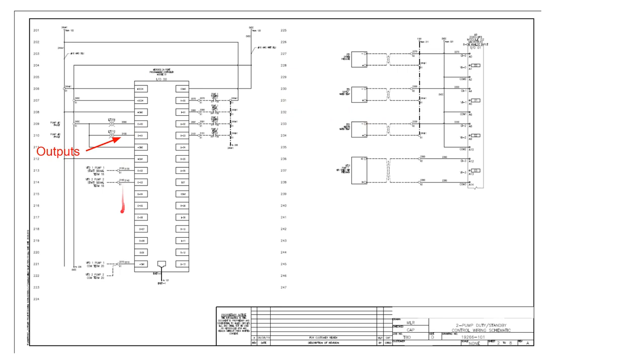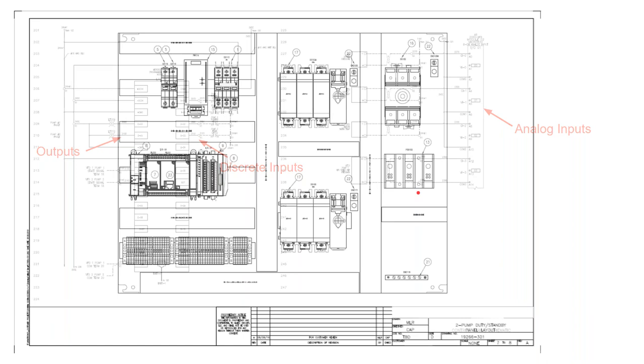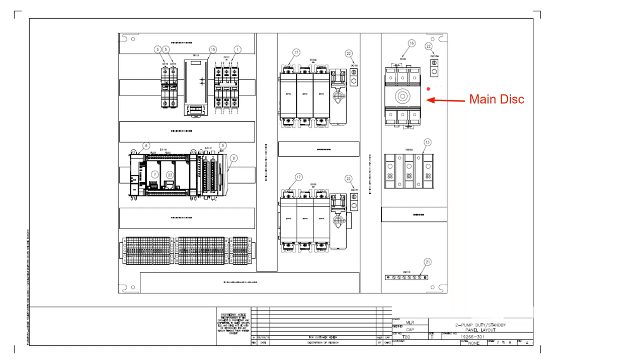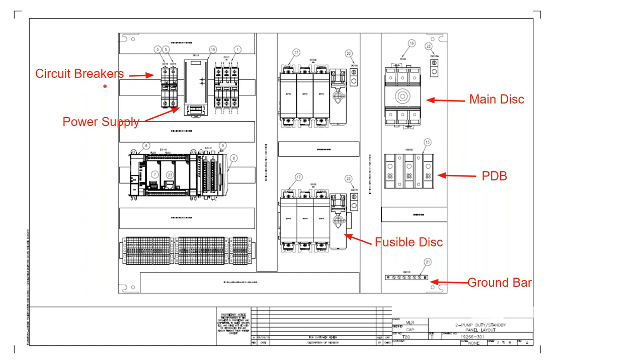On the outputs you can see the PLC control with various output relay coils. There are also discrete inputs, plus analog inputs — which are not on/off signals but rather continuous signals like temperature or pressure. All this information goes to the PLC to be processed in the program. In the actual panel build you can see the main disconnect, power distribution block, ground bar, fusible disconnects for the motors, circuit breakers for short circuit protection, and a power supply converting to 24VDC.